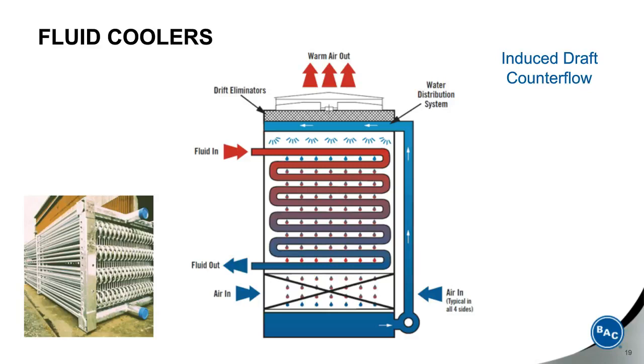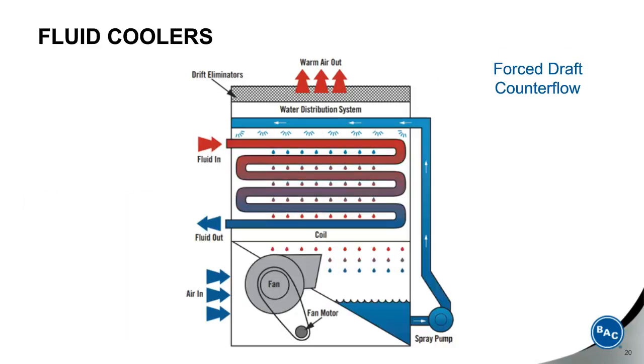And what we see on the left-hand side of the screen is a typical coil or tube bundle that is installed in the closed circuit cooling tower. Another type of closed circuit cooling tower is a forced draft counterflow, and this particular one is based on a centrifugal fan unit, which again can be good for indoor applications that can handle external static pressure, but it basically works on the same principle, except the air is forced up through the tube bundle with the fan at the bottom.